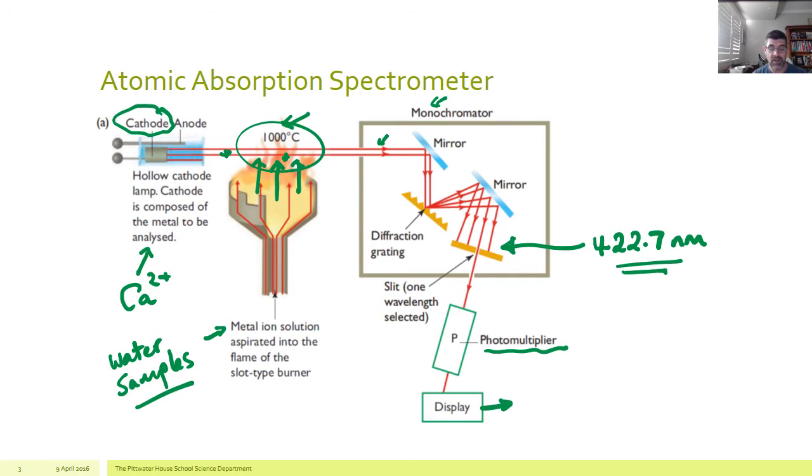So the way that most atomic absorption spectroscopy works is that we actually start with a series of known concentrations for the substance that we're looking at. So we would start with, say, a few different known concentrations of calcium solutions, and we would test them and we would find their values.